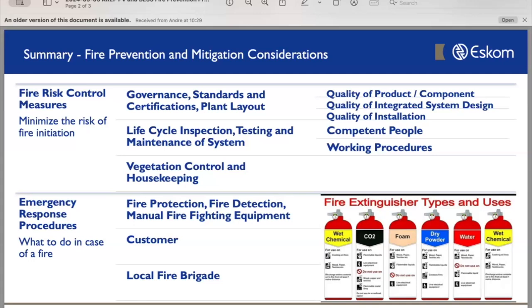We must start with fire risk control measures to minimize the actual risk of fire starting. As explained, it's critical to have governance standards and certifications of the components and systems we're installing, because mechanical damage and similar issues to batteries need to be controlled. There are now standards for quality control to ensure that if a battery is certified according to those standards, you get better understanding and quality of the product.